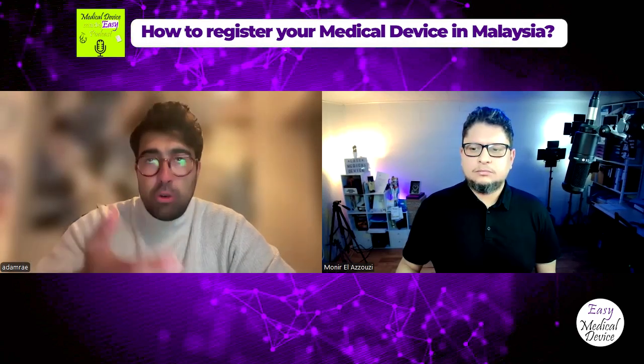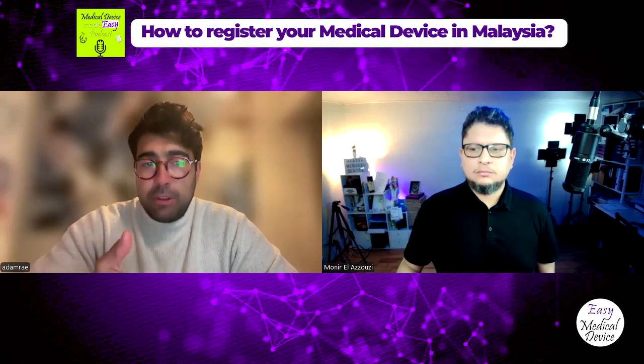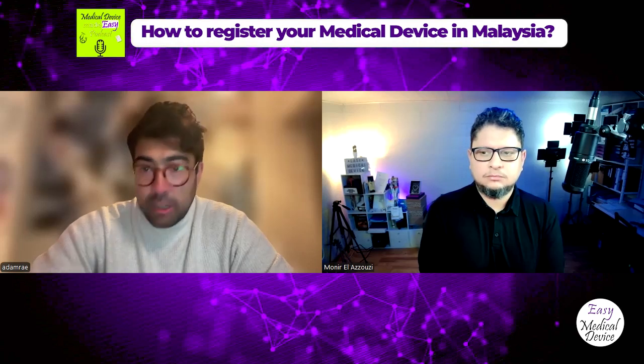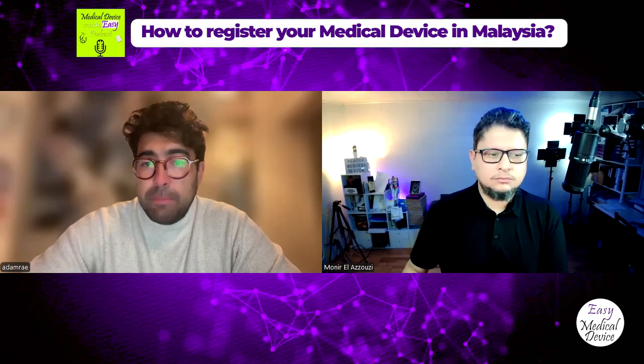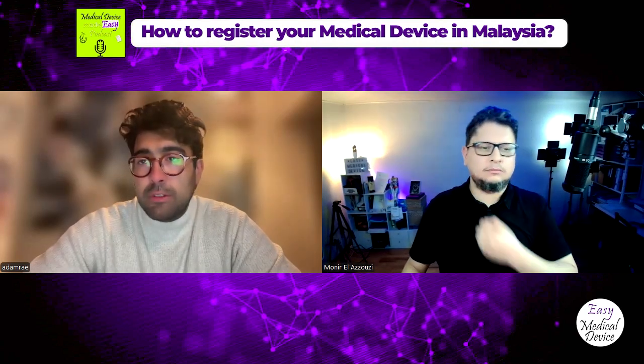Yeah. So there's a specific document we can post in the show notes that goes through the language requirements. It says home use devices must have Bahasa Malay. Any other devices can use English, and it specifies the use if they want to put other languages on there. So yeah, we can pin that document for the audience.